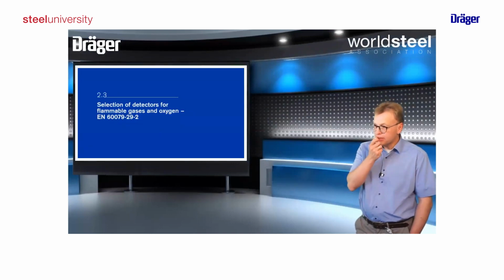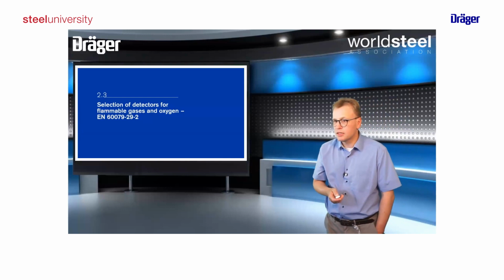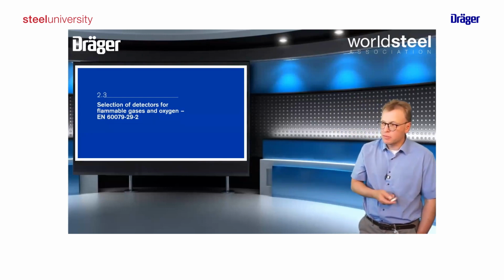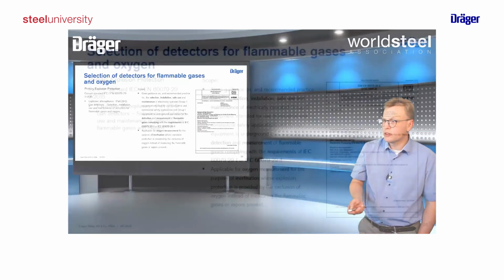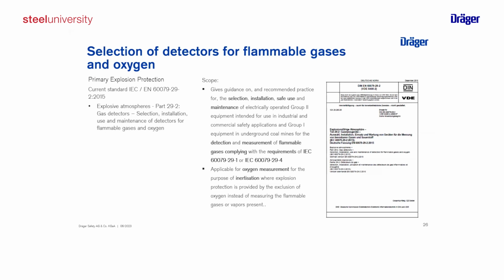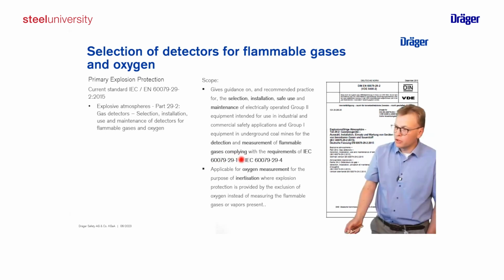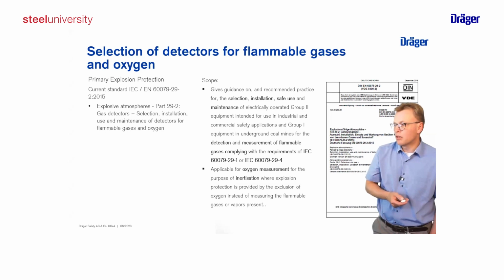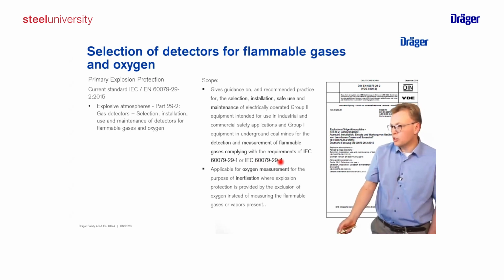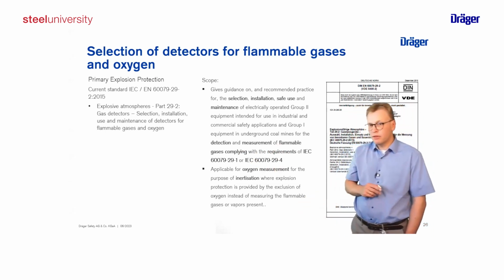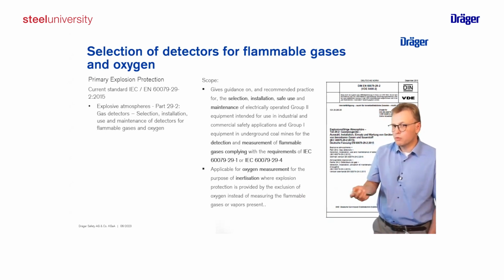Coming to the third part of my presentation, this is about how to select the detectors, because we want to detect flammable gases and especially now hydrogen. There's a standard, the 79-29-2. This is about the selection, and right in the beginning we see the scope, which says that the requirement for using gas detection is that it needs to comply with 29-1 and 29-4. 29-1 is for point detection, 29-4 is for line of sight. So if you follow this guidance and use it for primary explosion protection, the equipment selected based on this should be compliant with these performance standards.